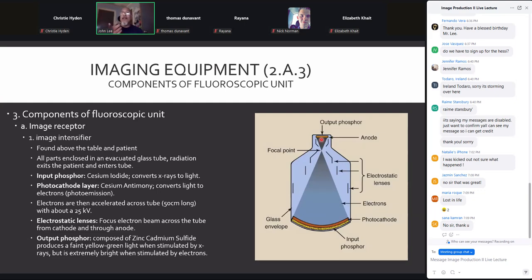The output phosphor is on the other side of the anode. Now, the anode, instead of being a large disk that the electrons strike, is a metal disk with a positive bias that attracts the electrons, but because it's got a hole in it, it allows the electrons to pass through and they strike the output phosphor, getting converted to a very, very intense light.